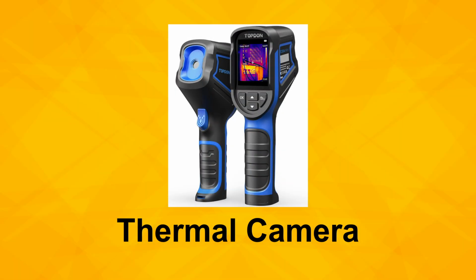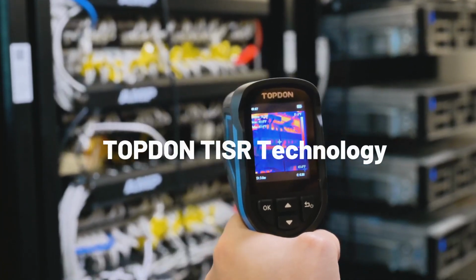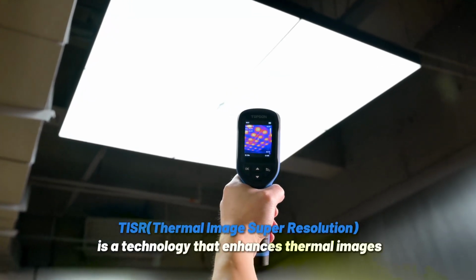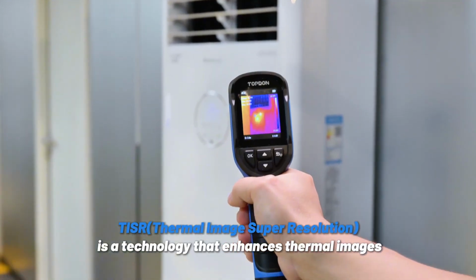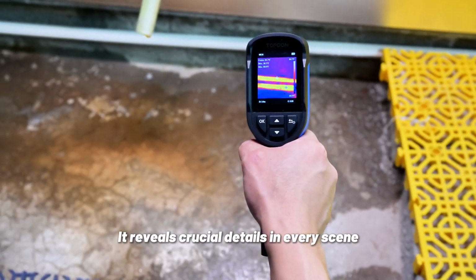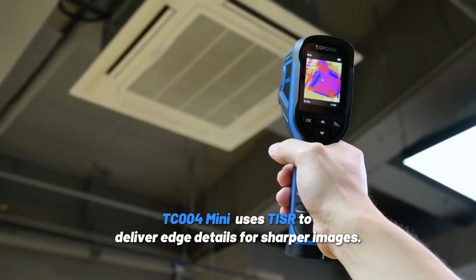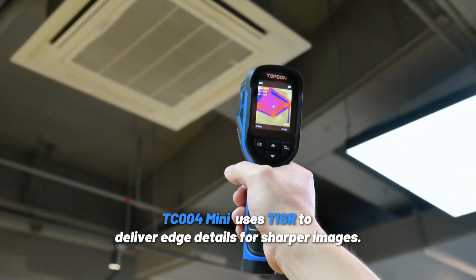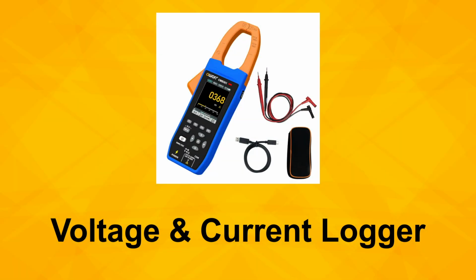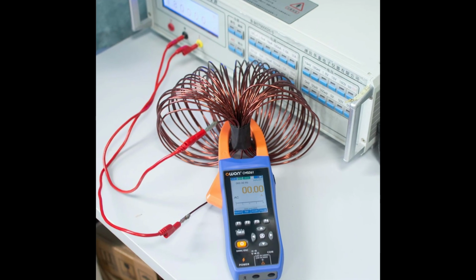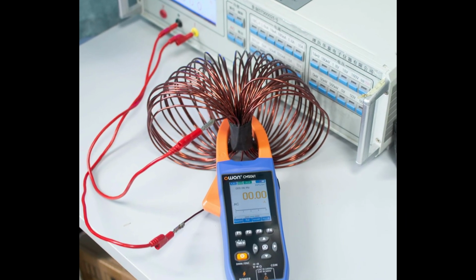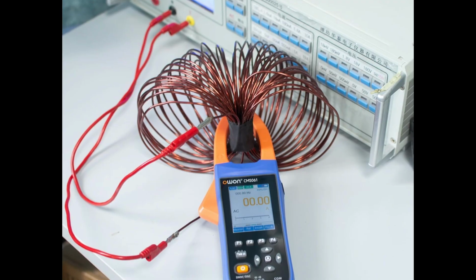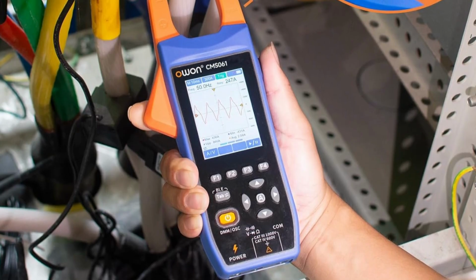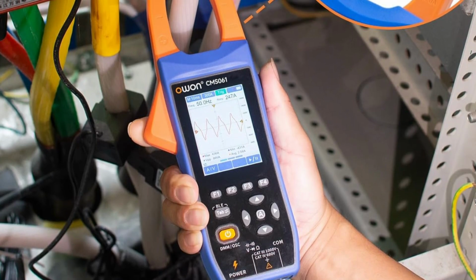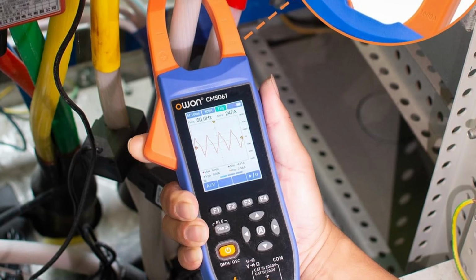This is a thermal camera. It reveals heat patterns in electrical systems, showing hot spots, loose connections, or overloaded circuits. Instead of guessing, you can spot issues instantly through the color display, making troubleshooting much faster. This is a voltage and current logger. It records electrical behavior over time, letting you track how a circuit performs during the day. It's helpful for finding random power drops, spikes, or overloaded equipment that don't show up during a quick test.